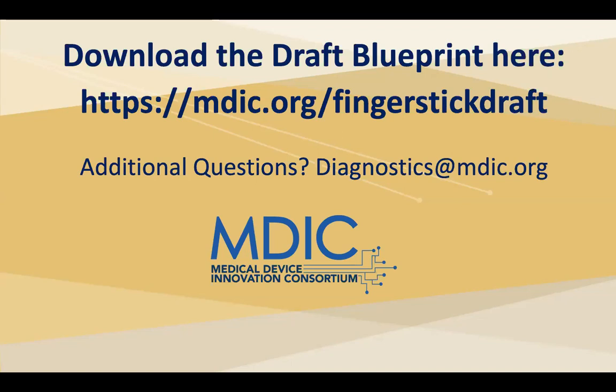Okay. Which study design approach should a fingerstick collection device, not a POCT, follow, waived or non-waived? I'm not sure I understand that question. Yeah, so this guidance, or waived or non-waived, applies to mostly analytical tests, not for collecting the sample, as I understand. Yeah, not the collection devices, right? So yeah, it's for, for example, a point of care glucose meter, not fingerstick collection devices.